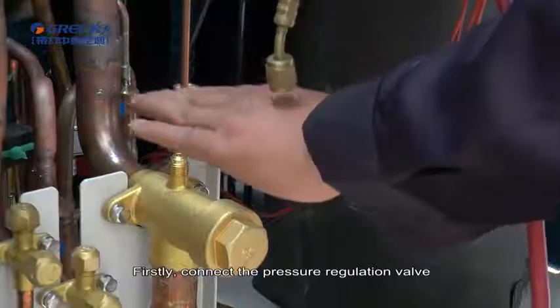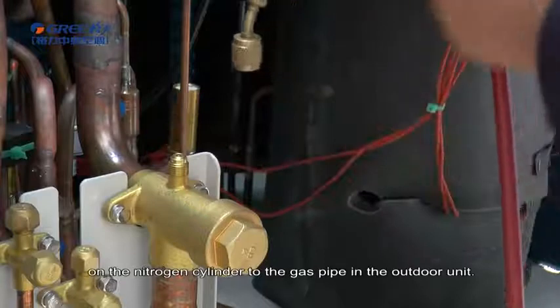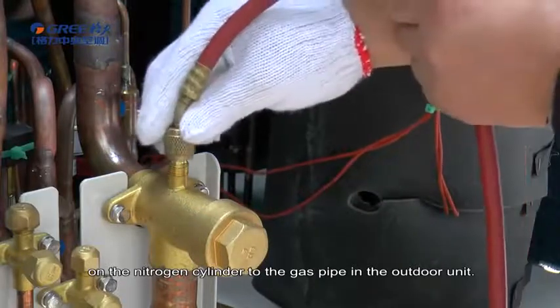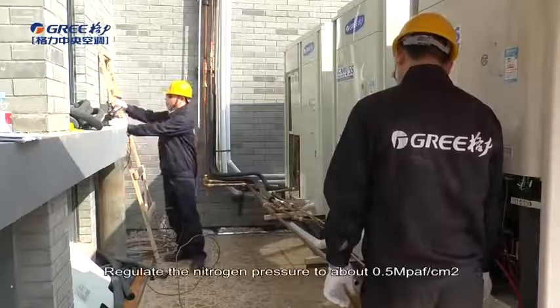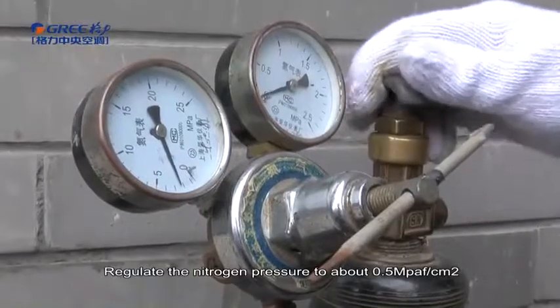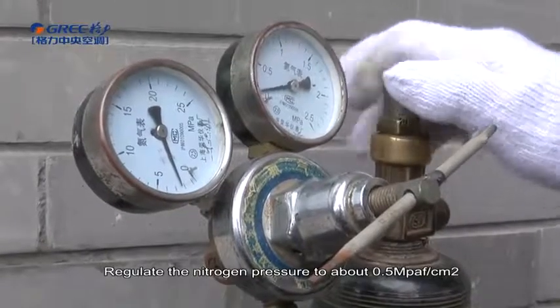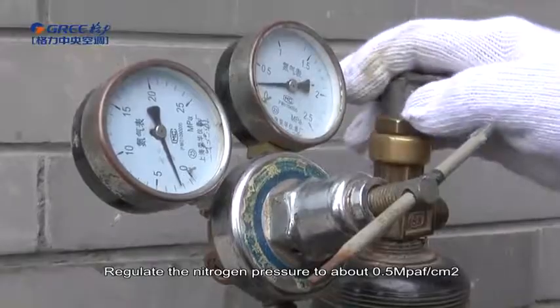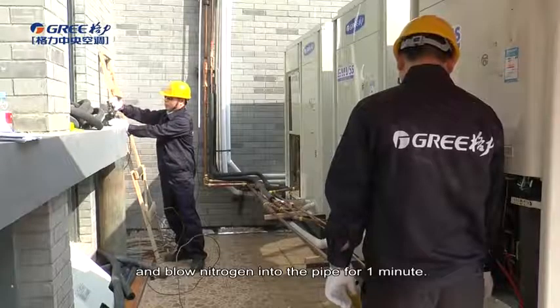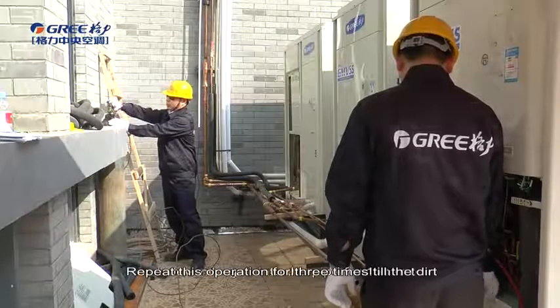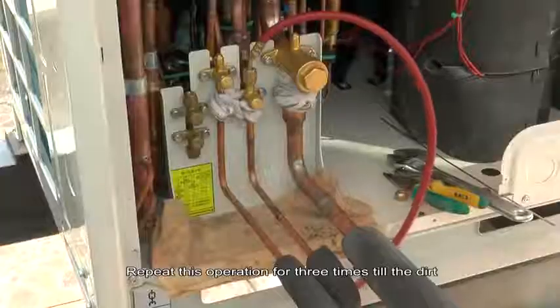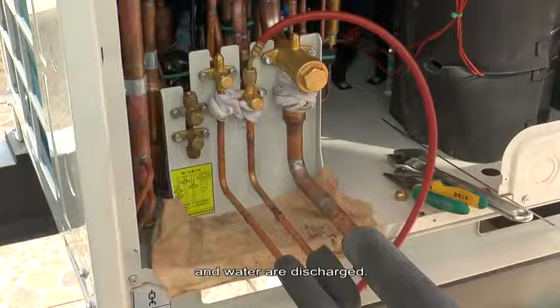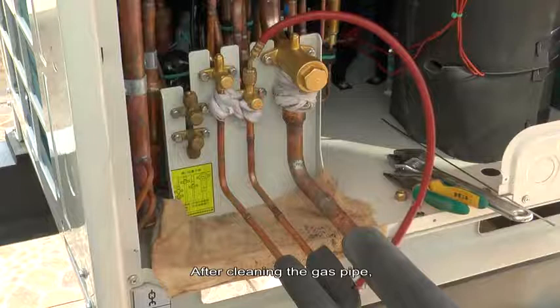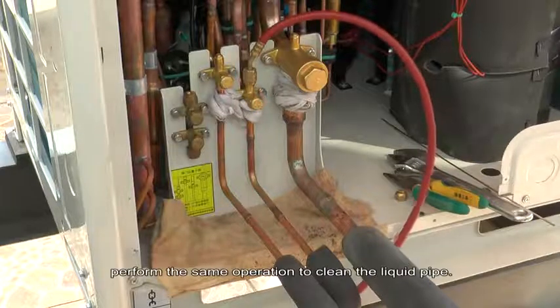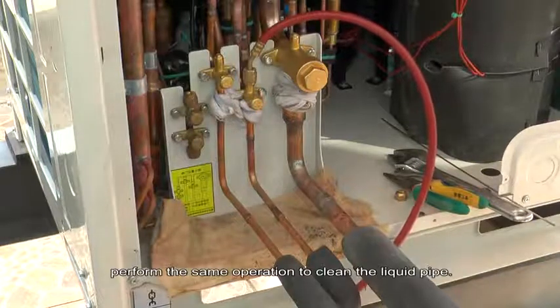Firstly, connect the pressure regulation valve on the nitrogen cylinder to the gas pipe in the outdoor unit. Regulate the nitrogen pressure to about 0.5 megapascal and blow nitrogen into the pipe for 1 minute. Repeat this operation for 3 times till the dirt and water are discharged. After cleaning the gas pipe, perform the same operation to clean the liquid pipe.